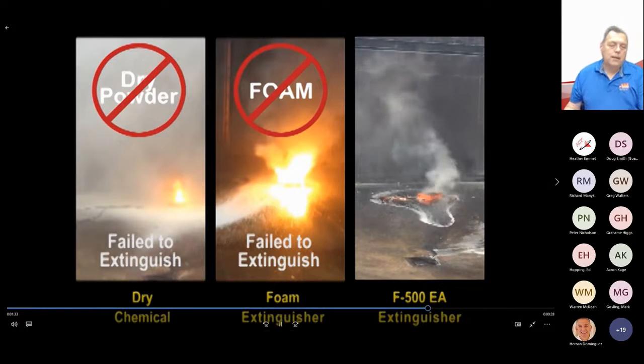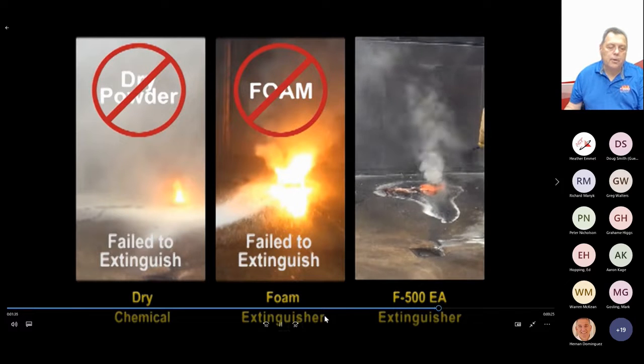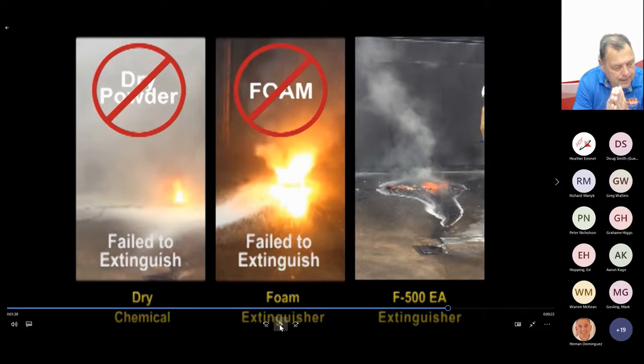So when I see this video and start to think about this hazard, again it's a multiple type hazard, and by default we seem to want to treat this like it's a Class A fire. And we know that ABC dry powder fire extinguisher is the #1 extinguisher sold in the world. And if this is an A fire and an ABC can't put it out, that makes me think perhaps we're not really dealing with an A fire.